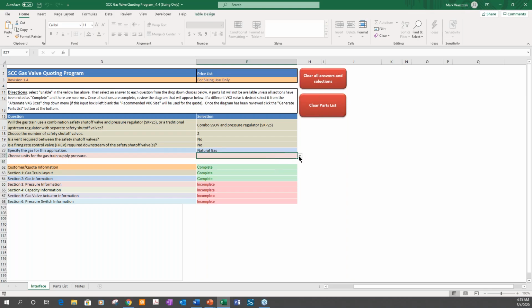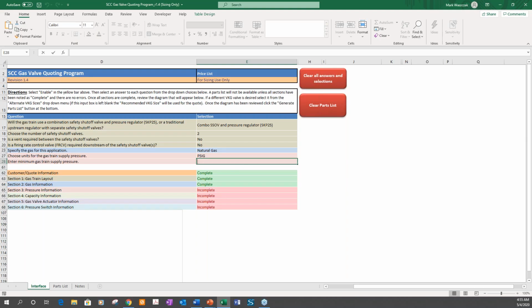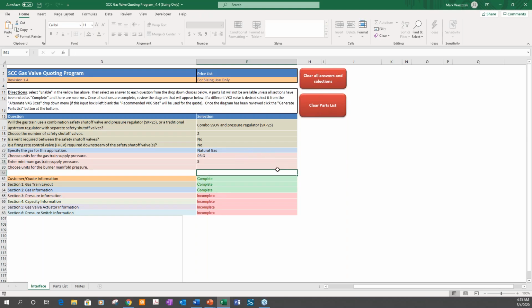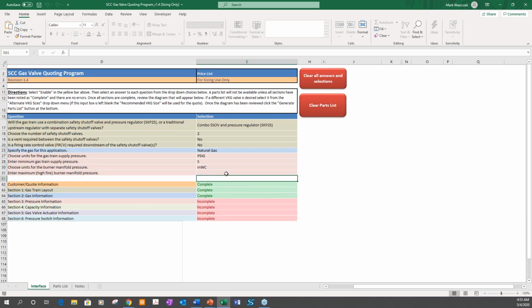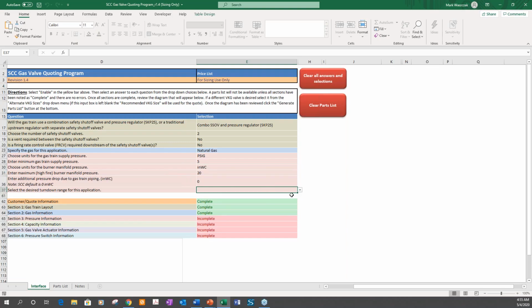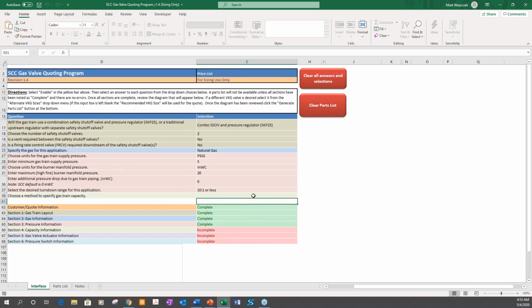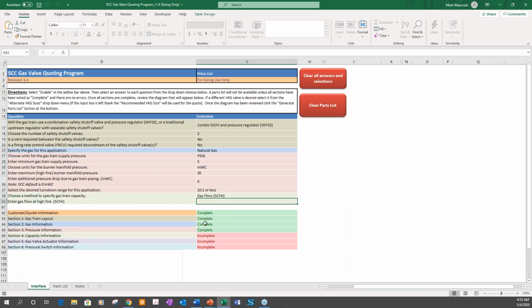Choose your units for your gas train supply pressure. In this case, it's PSIG, and we're going to choose 5 pounds. What is the burner manifold pressure, or the units for it? Inches water column, and we're going to select 20. Next, what is the desired turn down? Your options are 10-to-1, 15-to-1, 30-to-1, or greater than 30-to-1. For our application, we will choose 10-to-1. Choose the method to specify the gas train capacity. We're going to go based on gas flow, and we're going to choose 21,000.